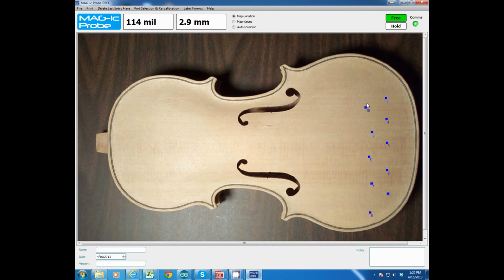You can go to File and you can go to the pre-map mode. This adds some options here to the top called Map Location and Map Values. So how this works is that you can actually pre-plan the locations where you're going to be measuring for this particular measuring session. So when you click on Map Location and then click on the screen, it actually starts putting a numerical sequence of dots on the actual picture itself. So you can then pre-plan to say, I want to start measuring here, my next measurement's going to be there, then there, and there, and there, and so forth. And you can just continue placing these dots, which are again pre-planned locations where you're going to be measuring.